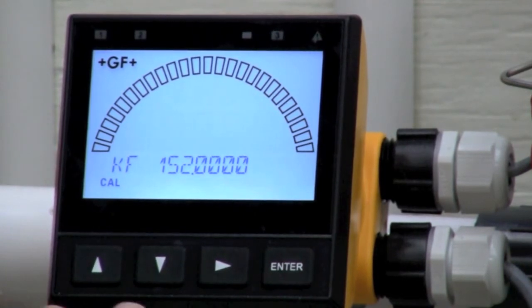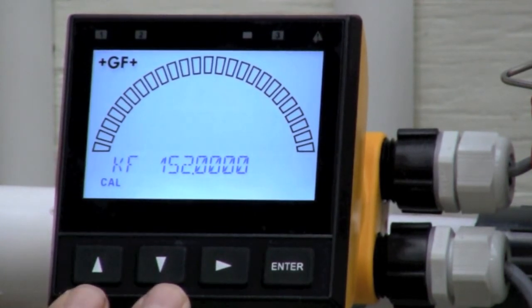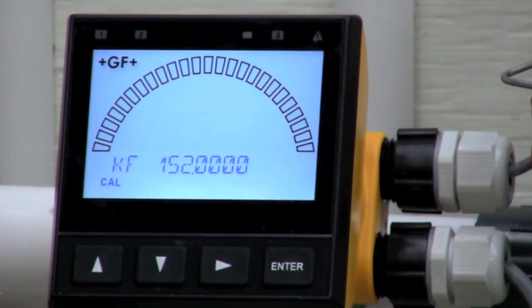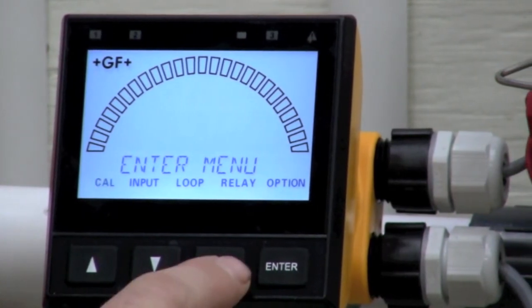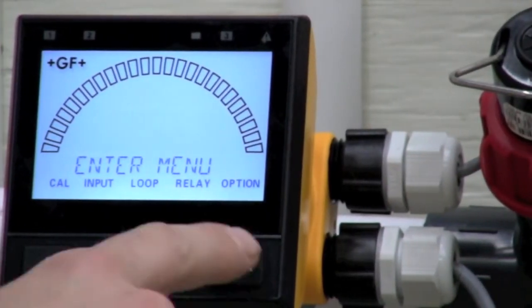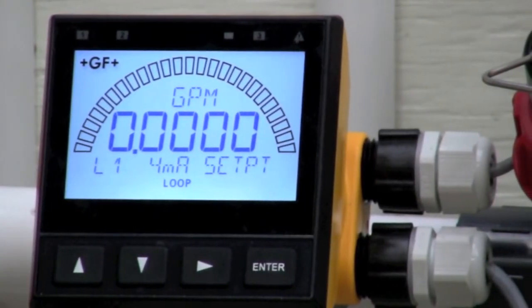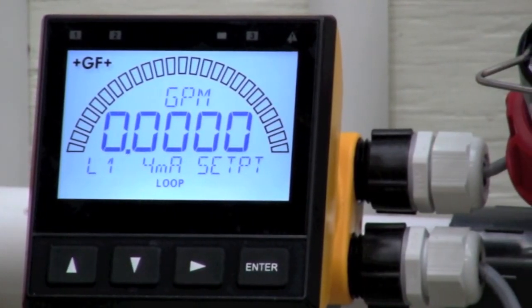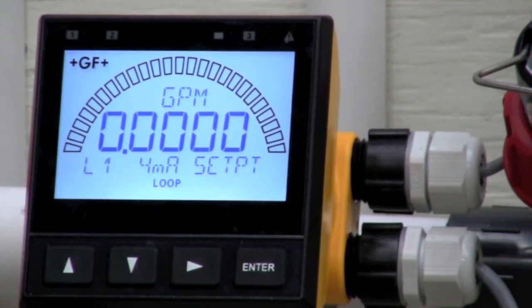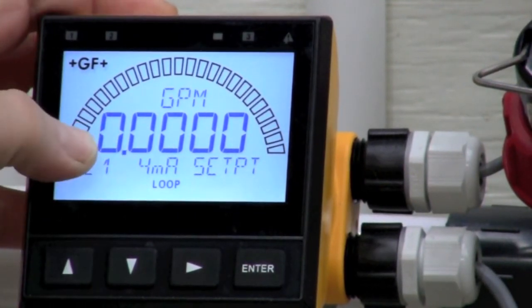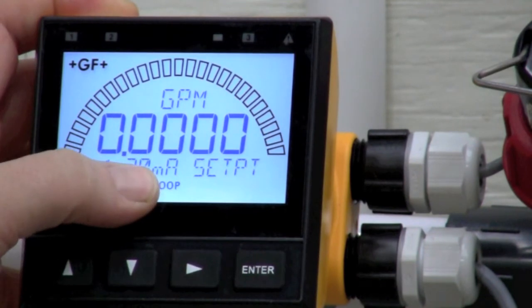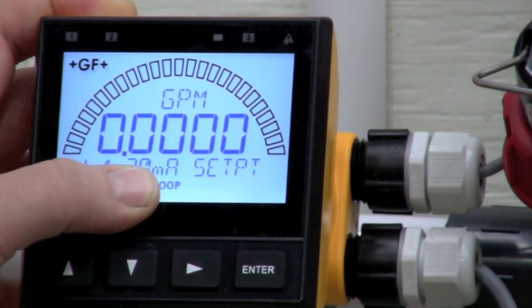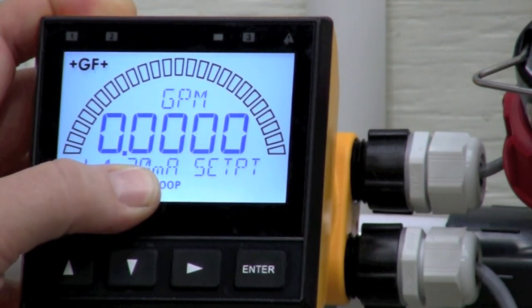To back up, I'm going to simultaneously press both of the up and down arrow. Every time you do this, it backs up one menu. I want to set my 4 to 20. I'm going to set my 4 to 20 for 0 to 15. Right now, 4 milliamp, factory default, 0 GPM. I agree with that. I'm not going to change it. I'm going to scroll down. 20 milliamp. I want my transmitter to output 20 milliamps when I hit 15 GPM.